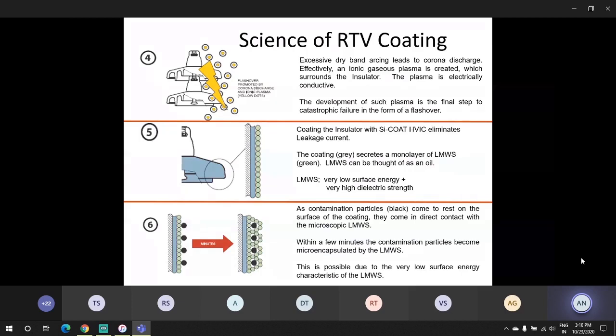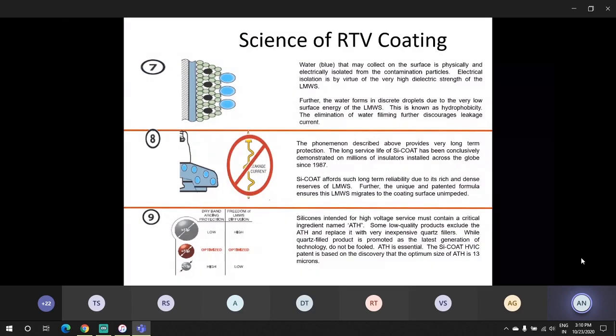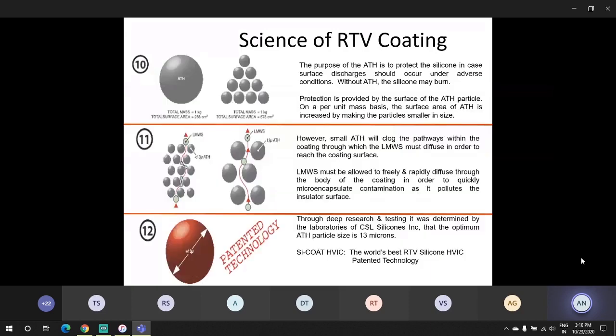The science is the same as the polymer insulator. So the key to this technology is that water is prevented from coming into contact with the pollutant, and the insulator surface is kept dry, and because the insulator surface is kept dry, there is no electrical discharge activity on the surface of the insulator. Each manufacturer follows a different size of the molecules. In our case, it is 13 microns.